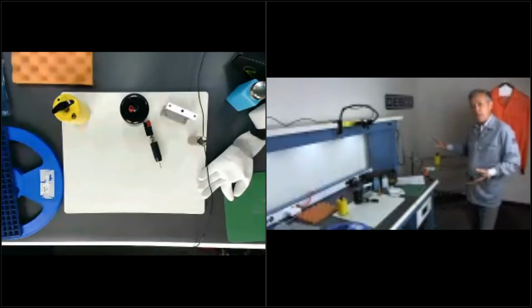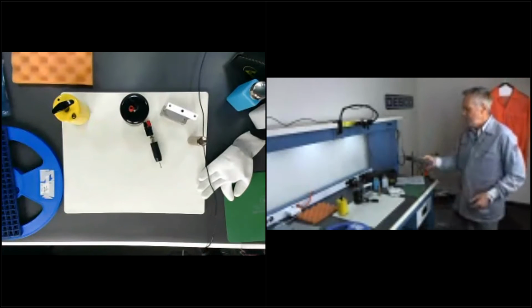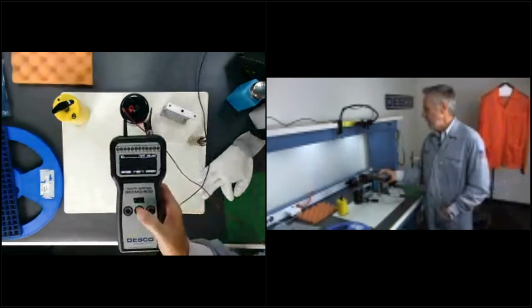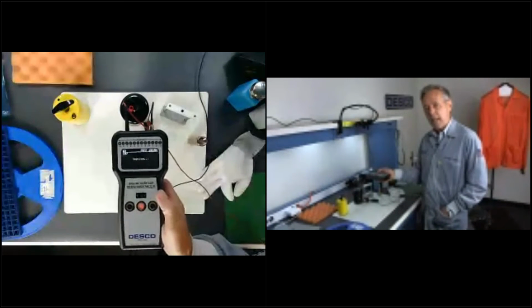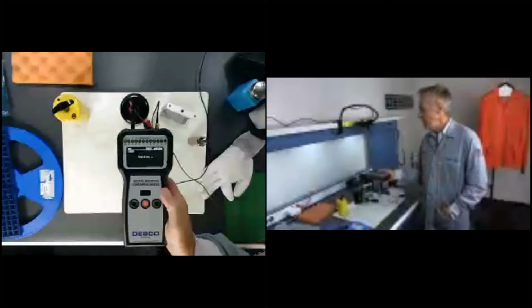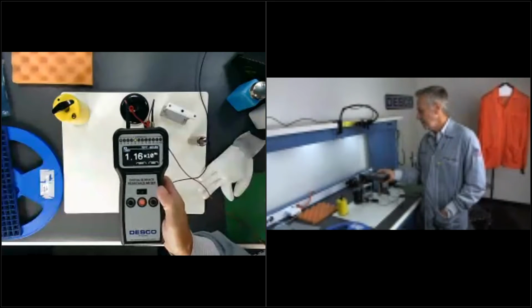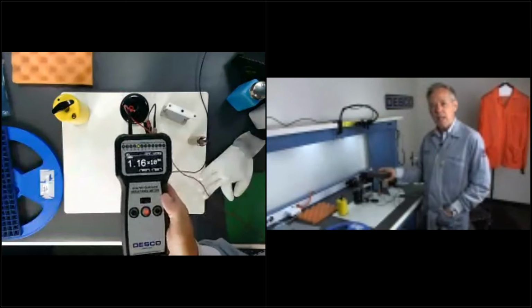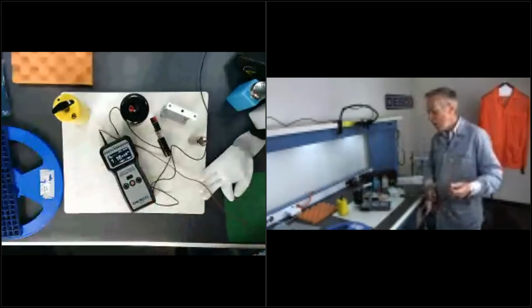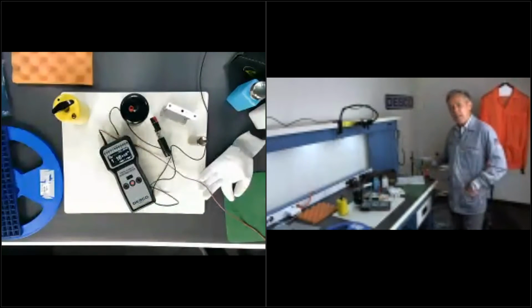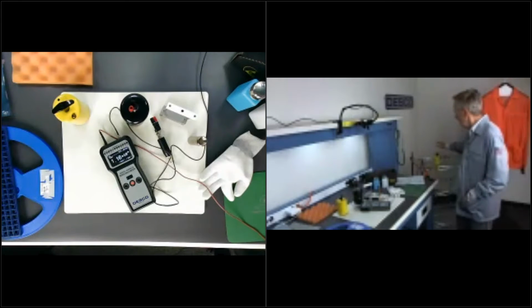Now I'm not going to do every measurement for a cart, but you would measure each shelf, for instance. I want to verify that not only is the cart grounded to the floor properly, but also within spec. And the spec is less than 1 × 10⁹ RTG. So 1.16 × 10⁶, well within that standard. Now your carts may have dissipative matting on them, or your tray liners, things like that. And again, you would just put this weight on whatever surface you have.